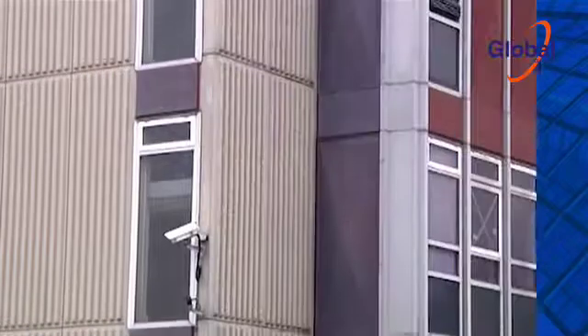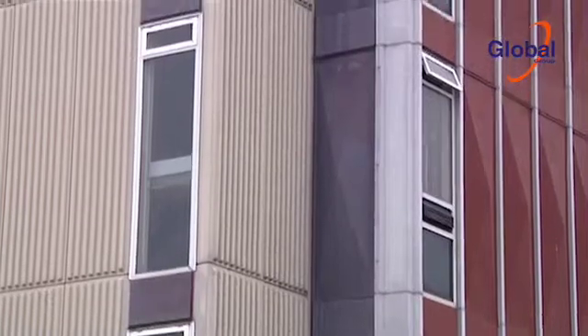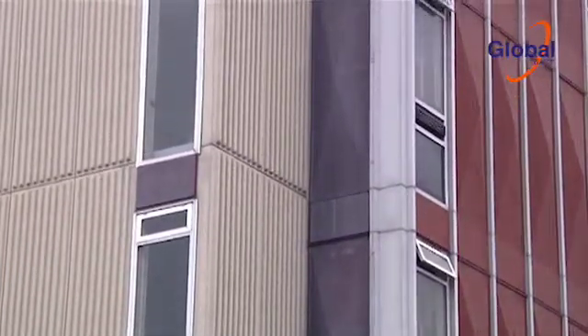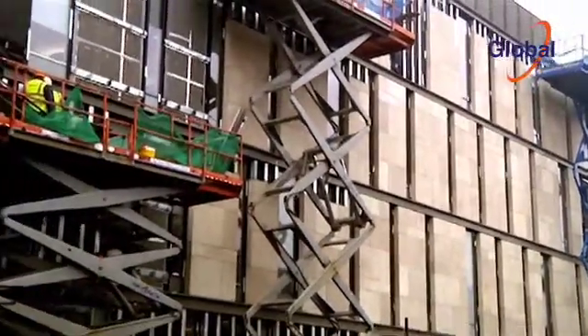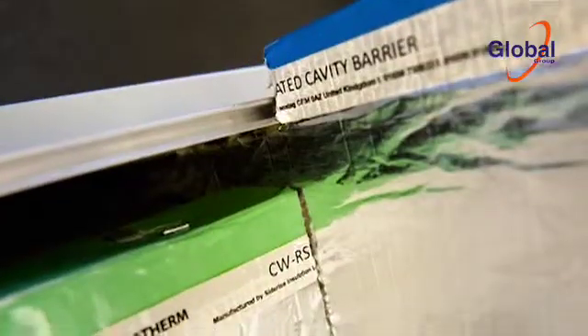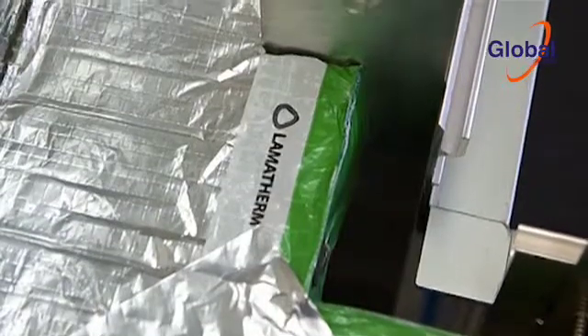If a building has external cladding, a fire at a lower level can spread up the face of the building, behind the cladding, and re-enter the building higher up. Several fires have resulted in fatalities due to fire spreading in this manner. When high-rise buildings, like offices and flats, with a rain screen or external cladding are being assessed, particular care needs to be taken that suitable cavity barriers are installed.